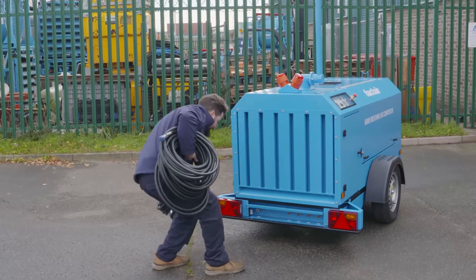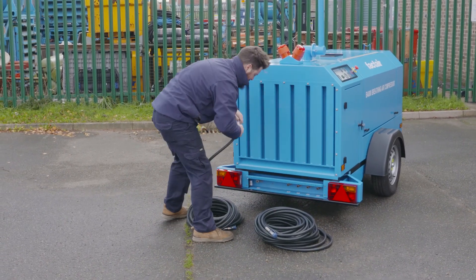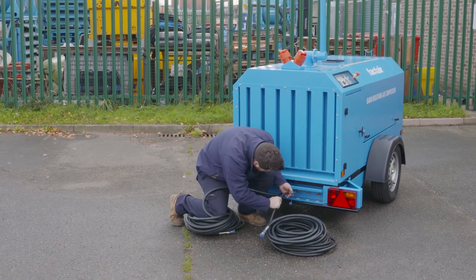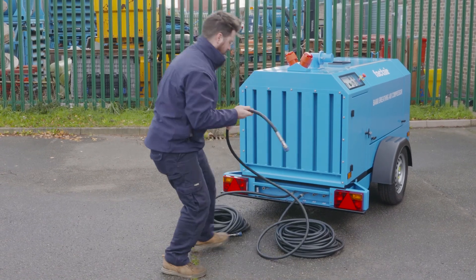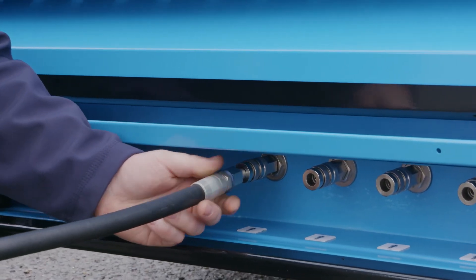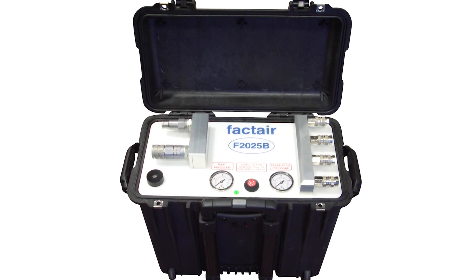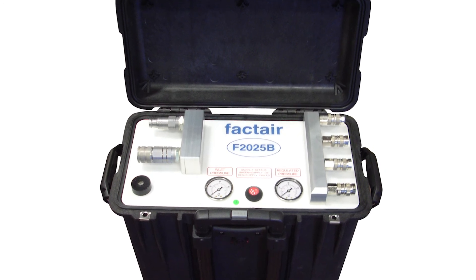Hose management is possibly the most difficult part of the system, therefore careful planning is of the utmost importance. As a general rule, the less hose you've laid out the better. If you need to run hose out across a road, they must be protected by either steel tubes or properly constructed ramps. Anti-static PVC or rubber hose with CEJN342 connections are available and can be connected directly to the breathing air compressor. Alternatively, where you need to deploy the BA800D a distance away from the worksite, the F2025 four-outlet flow distribution cabinet is available.